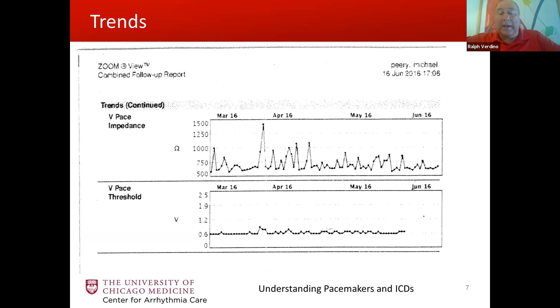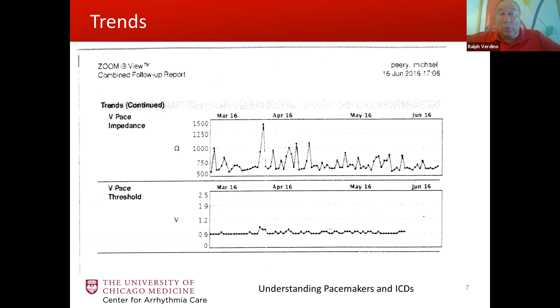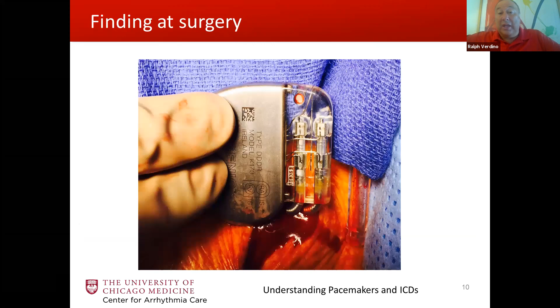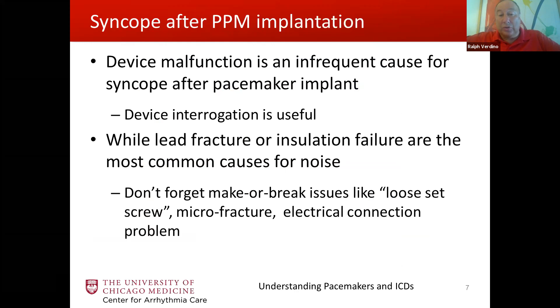So, 600 is well in the normal range, but if it had been a high impedance lead that was 1100 or something like that, and the next time you see them at 600, that's a bit of a concern. Or if where you placed it, it had an impedance for years of 300, and then it goes up to 600 or 700, that may be a little bit of a concern. So you like the impedances to be pretty stable over time, and most times they certainly are.